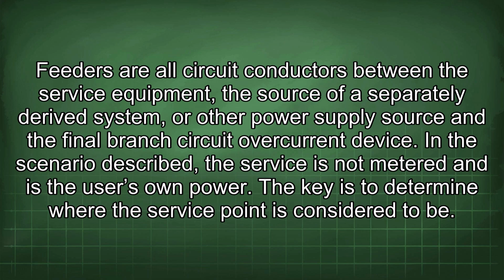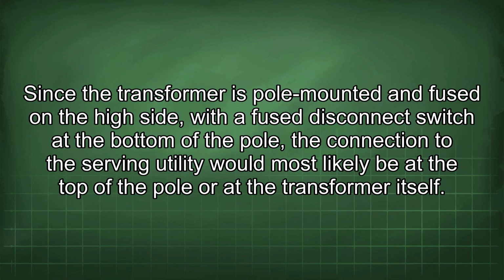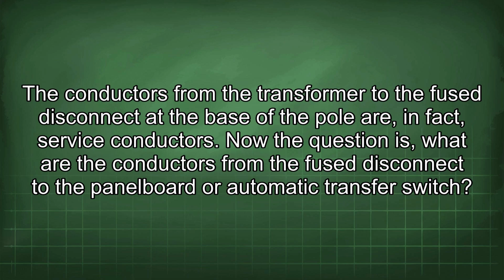In the scenario described, the service is not metered and is the user's own power. The key is to determine where the service point is considered to be. Since the transformer is pole-mounted and fused on the high side with a fuse disconnect switch at the bottom of the pole, the connection to the serving utility would most likely be at the top of the pole or at the transformer itself. The conductors from the transformer to the fuse disconnect at the base of the pole are, in fact, service conductors. Now the question is, what are the conductors from the fuse disconnect to the panel board or automatic transfer switch?